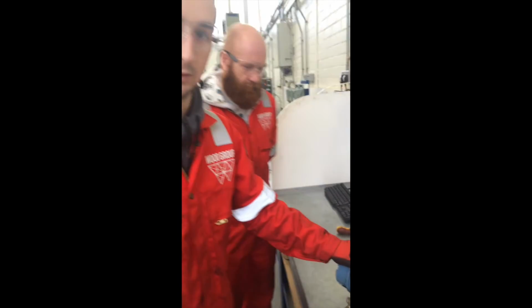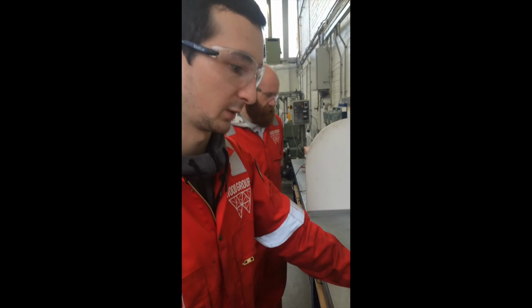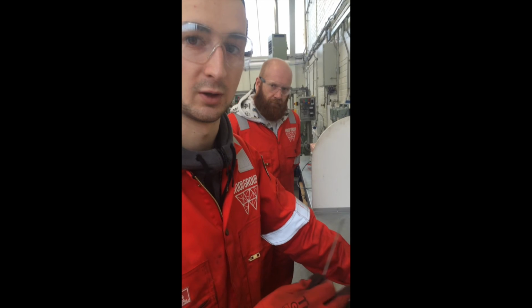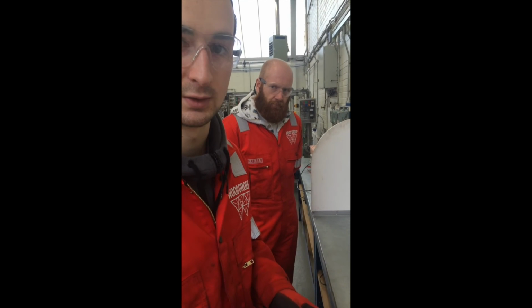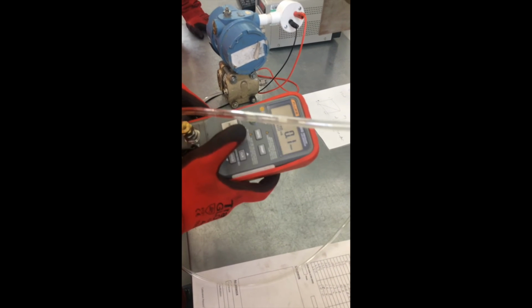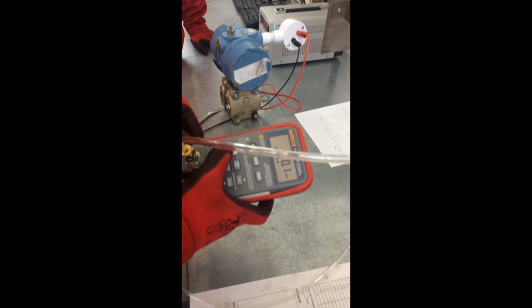That step's then repeated, so you go back down to 0 again and you take it back up to 250, and you do it a few times just so you get the same at each side and it's equal. Calibrated. We can set this back to 0 again, so we release the pressure out of it and then zero it.